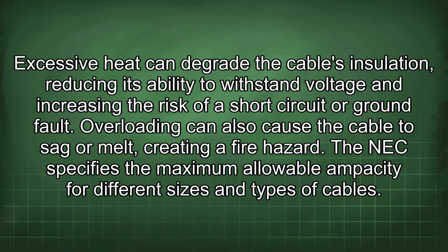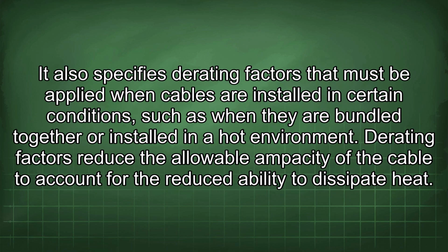The NEC specifies the maximum allowable ampacity for different sizes and types of cables. It also specifies derating factors that must be applied when cables are installed in certain conditions, such as when they are bundled together or installed in a hot environment. Derating factors reduce the allowable ampacity of a cable to account for the reduced ability to dissipate heat.